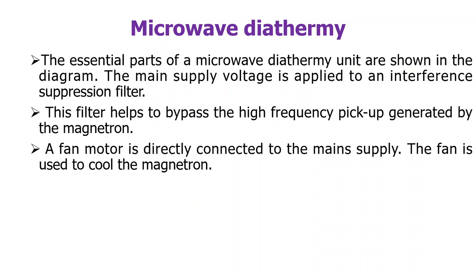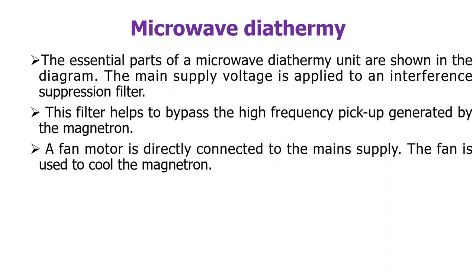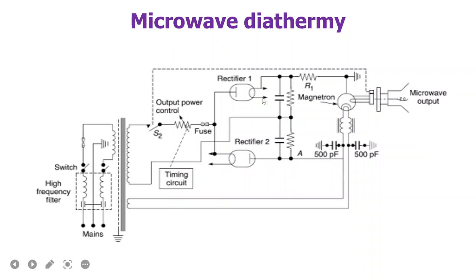The essential parts of microwave diathermy are shown in the diagram. There are filter arrangements for supply voltage suppression, and these filters also help to suppress high frequency interference generated by the magnetron. A fan is also used. In the diagram, the mains are connected to a transformer with a high frequency filter to avoid interference. The secondary of the transformer is given to a rectifier circuit, and from the rectifier the input is given to the magnetron. The magnetron acts as an oscillator and produces the microwaves, which are directed towards the antenna and reflector and sent to the body.